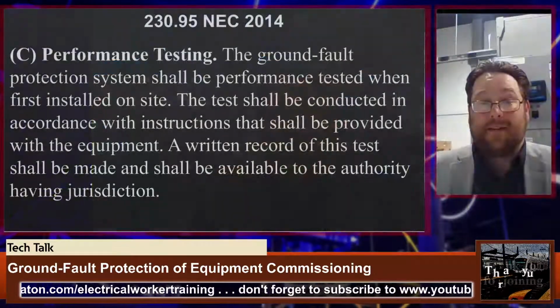Downstream in the system, that ground fault current obviously flowed the whole way back up through the main device, their only level of ground fault protection. And sure enough, it took the entire cancer treatment center offline temporarily. So it's really important to think through all these things, right? Ouch. Not just what do we buy, but how do we maintain it? What are all the other considerations for the system?